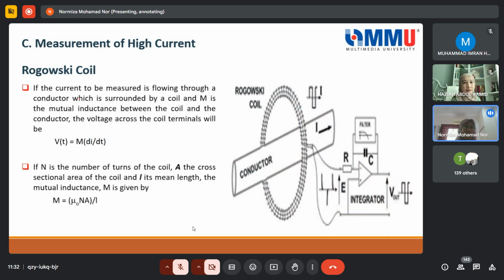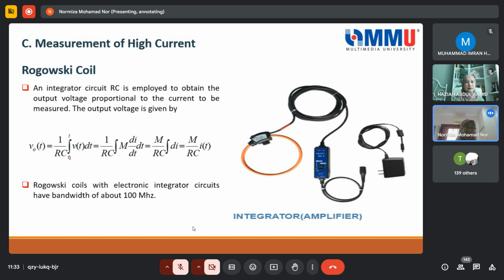So if the current to be measured flows through the conductor here, which is surrounded, and M is the mutual inductance, the voltage across will be M di over dt. The design has to consider the number of turns, the cross-sectional area of the coil and length L, and it gives you the mutual inductance M, which can later be used to calculate the current, where the current is proportional to this output voltage. So these are some examples of the Rogowski coil.